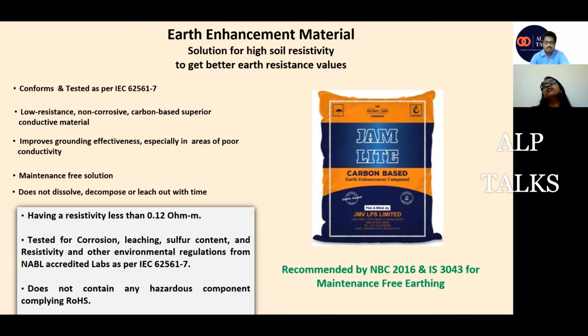As I'll tell you, with salt and charcoal we were having many limitations and disadvantages. First of all, salt and charcoal leaches out with time, so we require regular maintenance. Also, it corrodes the earthing conductor, and so these are the common problems which we generally face with salt and charcoal. To overcome these challenges, there are 4 or 5 types of tests which we generally perform on this chemical. The first one is the corrosion test, to check that it should not corrode my earthing rod. Only then will it be able to serve a longer lifespan of earthing.